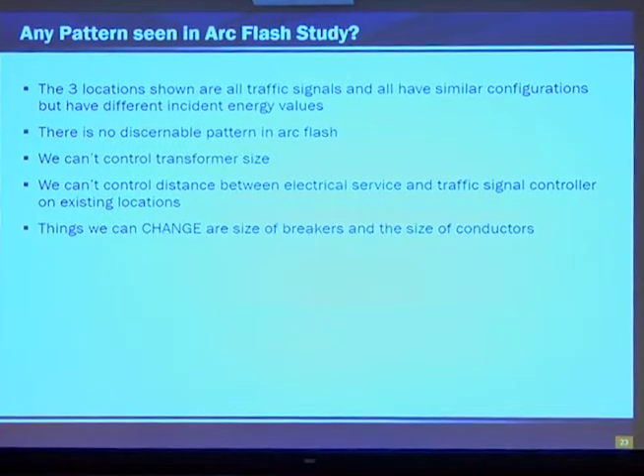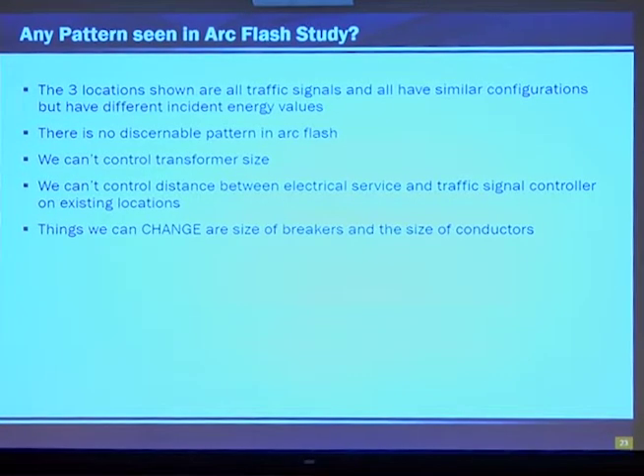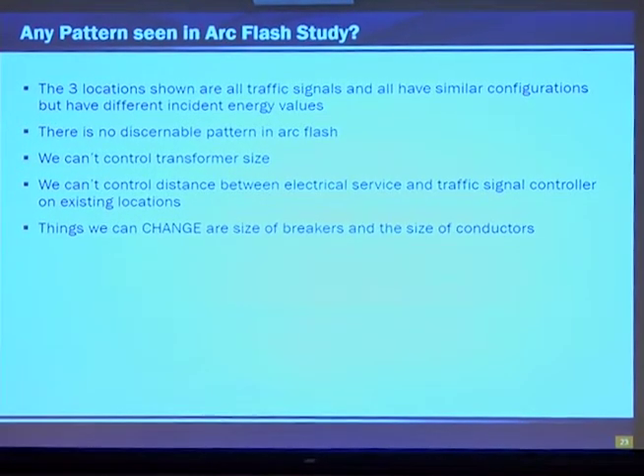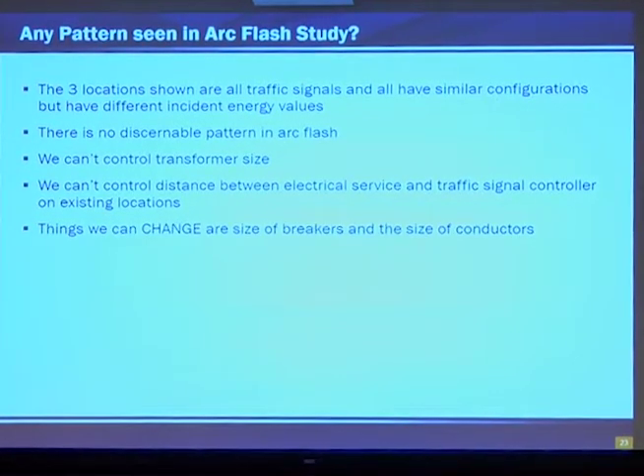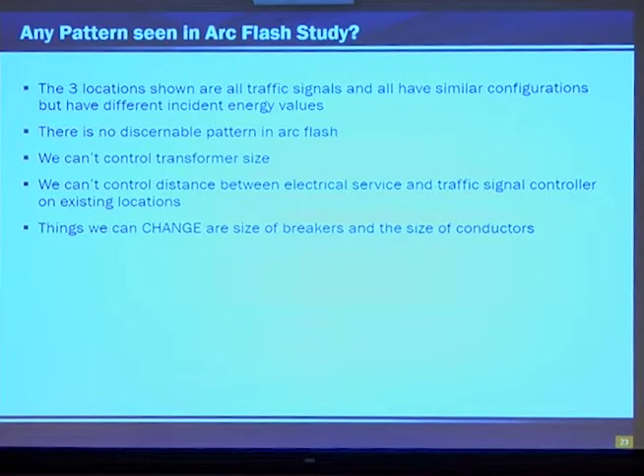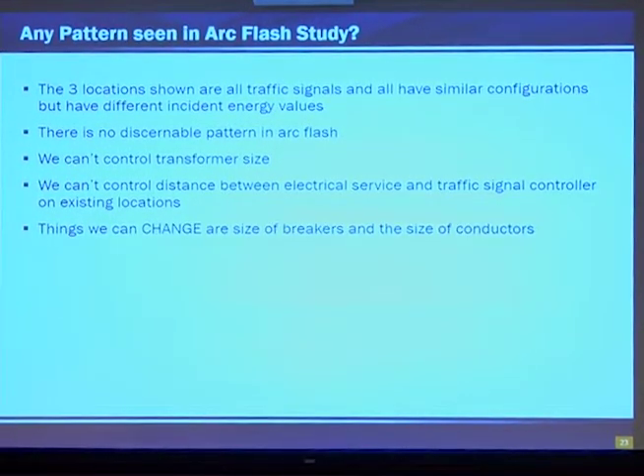We couldn't figure out what worked, what didn't work, why are they all coming out different? So there's stuff that we could control and stuff we couldn't control. So we figured out, well, what can we control and what couldn't we control? Well, we figured out we can't control the transformer size of existing installations. We can't control the distance between the electrical service and the traffic signal controller. But we started looking into things that we could control. So we could control the size of the breakers and the size of conductors from the design phase.